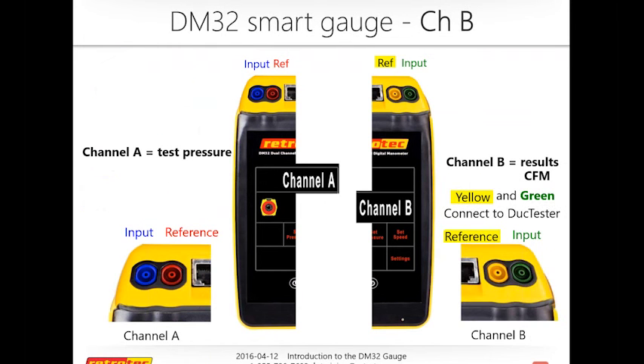Using the same test as an example, on channel B we would be looking for pressure inside of the fan, and that would be extrapolated to give us our flow. So here we would have the yellow tube connected to the duct tester, and the green tube connected to the duct tester. That's a little bit different if you're more familiar with the Energy Conservatory fans, the difference being that we are actually referencing pressures in the fan. So this is referencing pressures in front and in the back of the connection to the ductwork. And that's going to give you a really nice accurate reading.